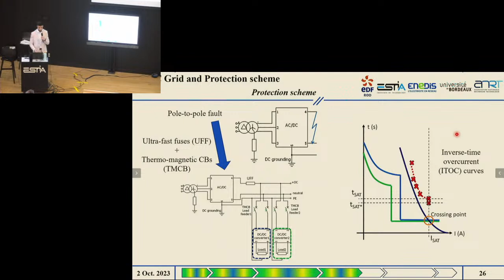And here I present the technique and the strategy that was used in this work to try to coordinate all these protection devices, with the final objective of reaching a selective protection scheme. The strategy was to use inverse time overcurrent curves, where the behavior of each component of the grid could be modeled: the thermal behavior of the power electronic converter in red, the behavior of the ultra-fast fuses in dark blue, and the behavior of the circuit breakers in light blue and in green.